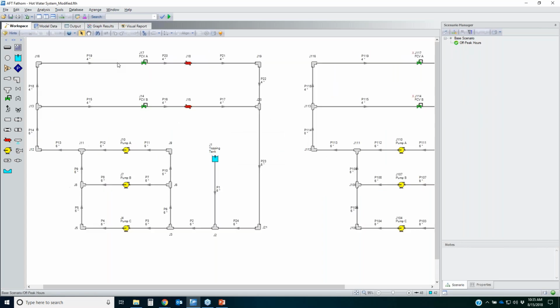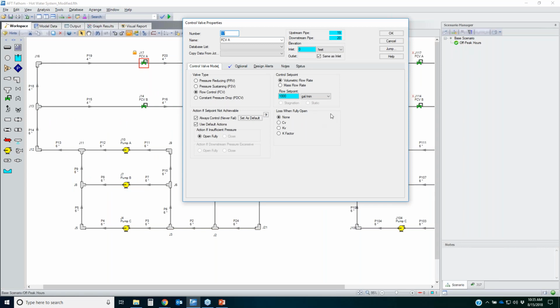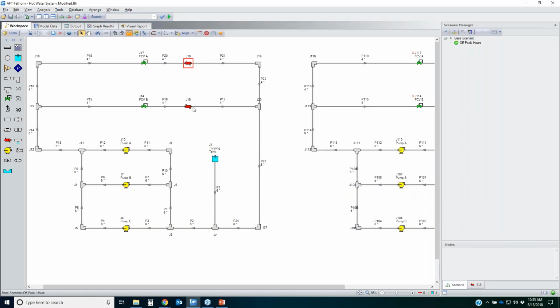So here's what I did. I've got, in my off-peak scenario, 1,000 gallons per minute through each heat exchanger. So instead of needing 1,500 GPM through each heat exchanger, I only need 1,000. That's a total of 2,000 gallons per minute system flow. So my left-hand system here is running the pumps at 100% speed and controlling with the flow control valves there.